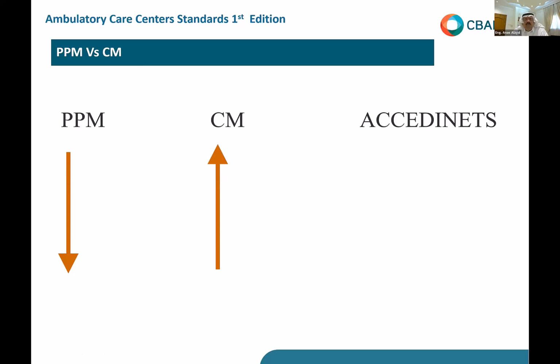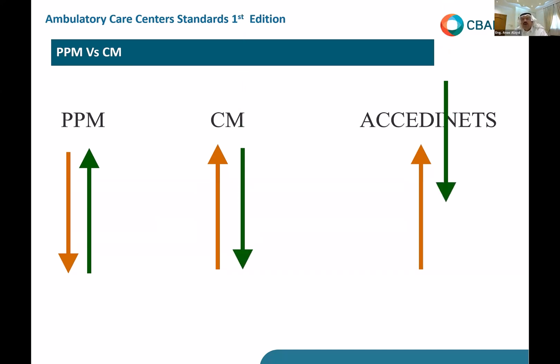Now, if you have a lower preventive maintenance, it's very bad. If you don't have preventive maintenance, then you have higher corrective maintenance. And it was very well, scientifically established that you will have higher accidents, because there is a correlation between corrective maintenance and accidents. So one of your aims or objectives is to increase PPM and decrease CM, so you can decrease accidents. On the other hand, if we are increasing the preventive maintenance, we are lowering the corrective maintenance and we are lowering the accidents.